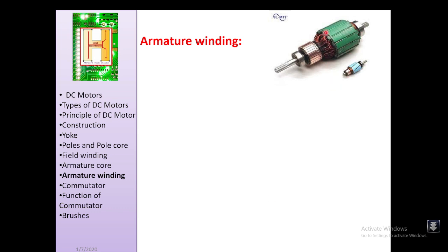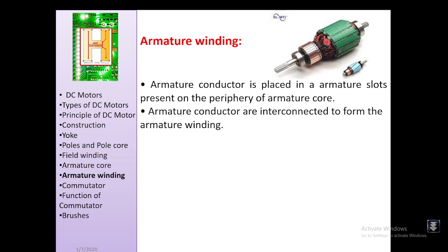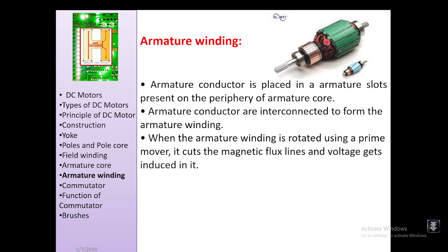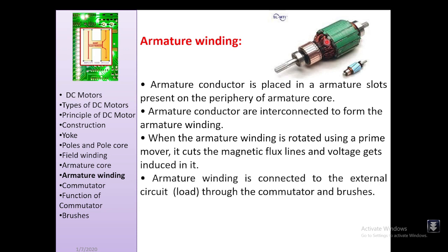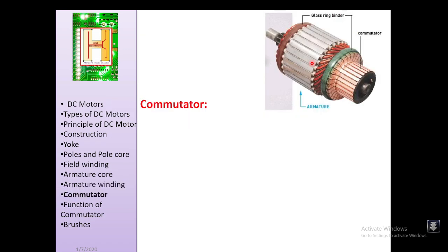Armature conductors are placed in the slots on the periphery of the armature core and interconnected to form the armature winding. When the armature winding rotates, it cuts the flux lines and voltage is induced. The armature winding is connected to the external load through the commutator and brushes. It is generally made of copper for long durability.